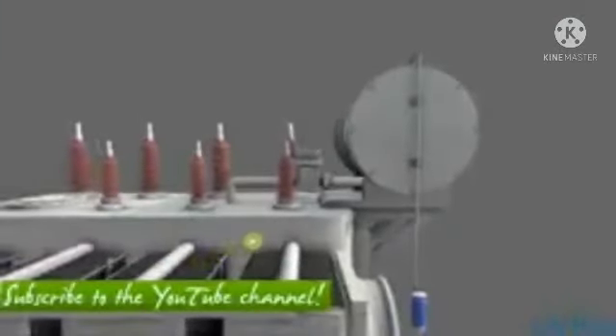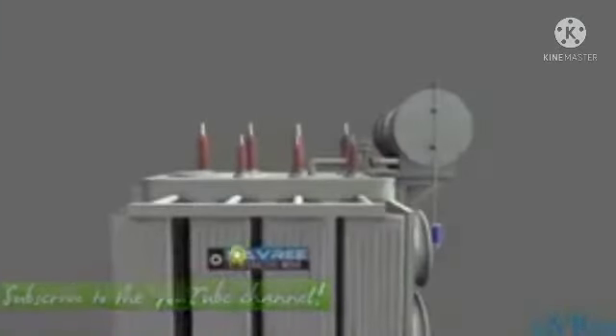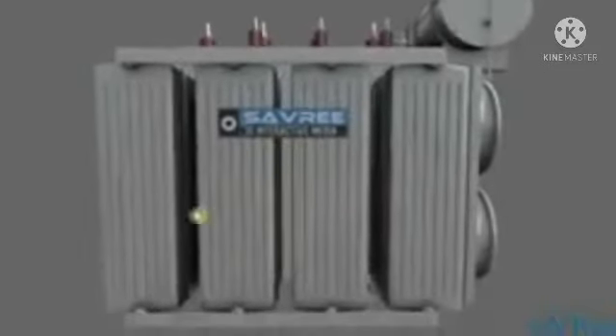If we zoom out, you can see that we have different cooling fins on the side of the transformer this time. The reason that these cooling fins are larger is because we need to get rid of more heat. I'll just rotate around the side. You can see that we've got an entire radiator this time. The liquid enters the top of the radiator, it cools down, and then it passes out the bottom.